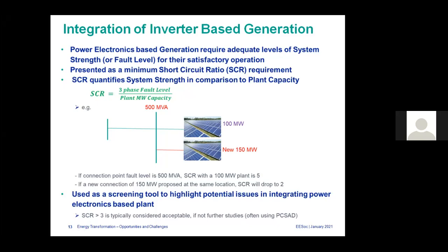Now, if the inverter manufacturer says their plant can withstand an SCR of 2, then we are okay. We don't really have to worry too much about this. But sometimes they might say, no, below 3 we can't guarantee stable operation. So what we normally do is use this SCR as a screening tool. Whenever we get a new connection application, we check the current fault level and the present asynchronous generation connected, like in this example. Then we add the new generator. If the resulting SCR is normally less than 3, we suggest you do more detailed modeling.